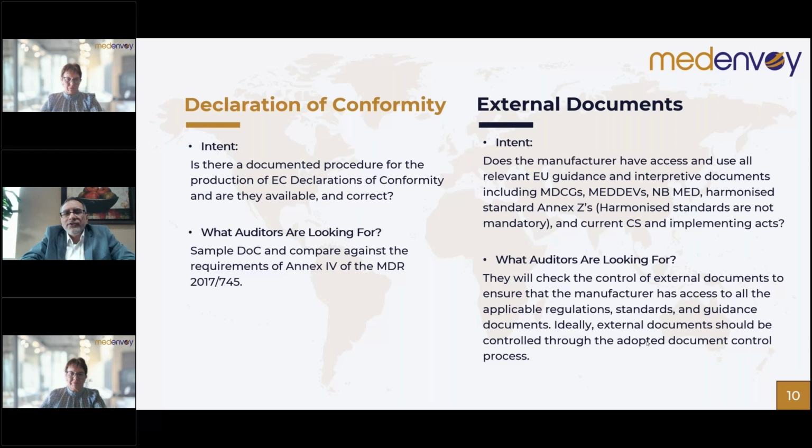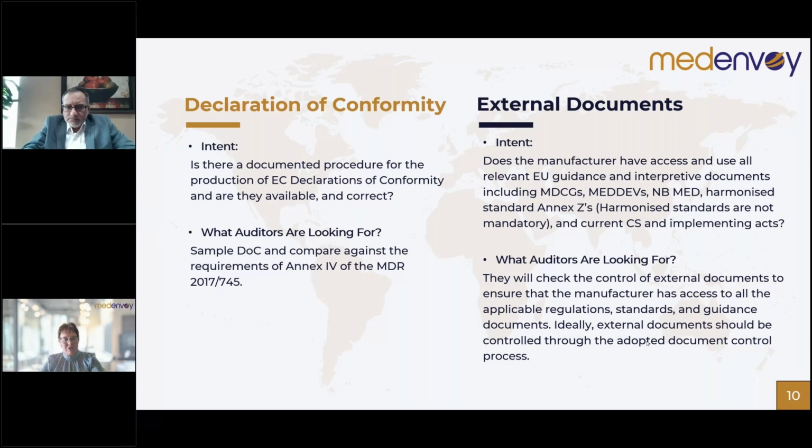Yes, I can. So you wanted me to speak about the declaration of conformity requirements for Switzerland? Yeah, so what we notice is that Switzerland has a specific requirement regarding DoCs of legacy devices. Just to remind all participants, Switzerland is not accepting declarations of conformity that are signed after the date of application of the MDR for legacy devices when addressing non-significant changes. So if you have non-significant changes, those changes need to be documented in a document accompanying the declaration of conformity, such that the original declaration of conformity that was signed prior to the date of application of the MDR is still there and valid as such. Excellent. So moving on to the next slide. Thank you, Danielle.